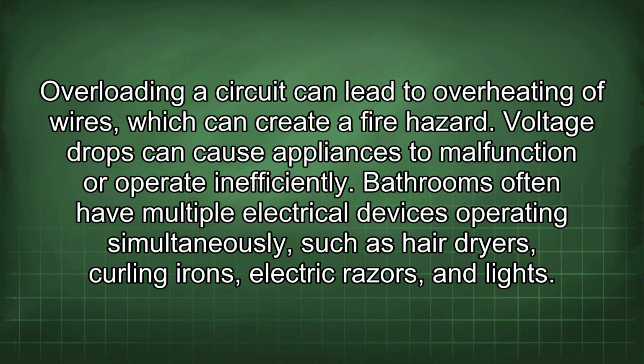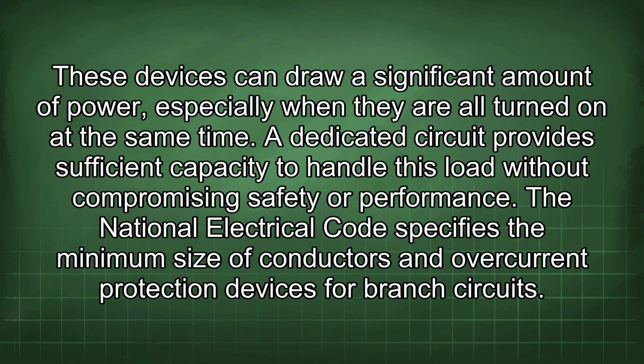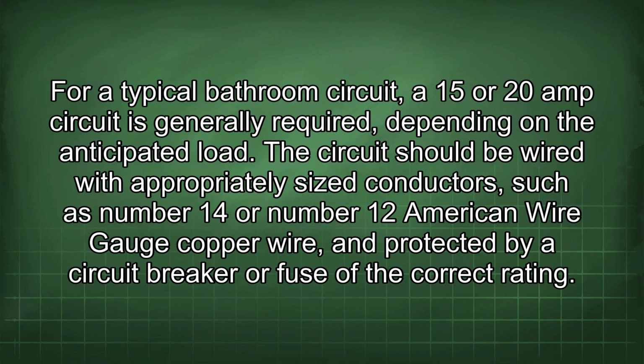Bathrooms often have multiple electrical devices operating simultaneously, such as hairdryers, curling irons, electric razors, and lights. These devices can draw a significant amount of power, especially when they are all turned on at the same time. A dedicated circuit provides sufficient capacity to handle this load without compromising safety or performance. The National Electrical Code specifies the minimum size of conductors and overcurrent protection devices for branch circuits. For a typical bathroom circuit, a 15 or 20 amp circuit is generally required, depending on the anticipated load. The circuit should be wired with appropriately sized conductors such as number 14 or number 12 American Wire Gauge copper wire, and protected by a circuit breaker or fuse of the correct rating.